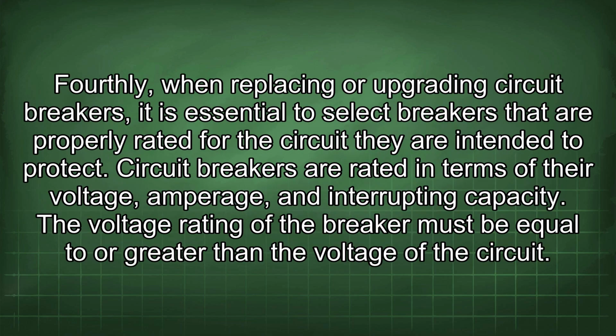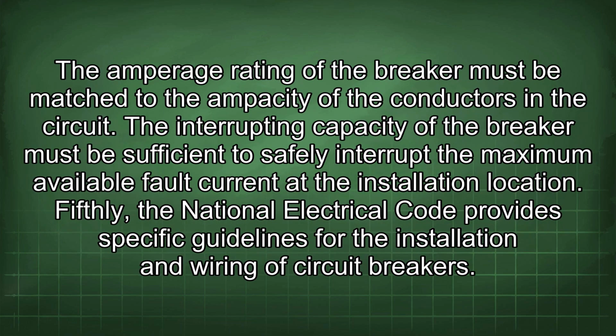Fourthly, when replacing or upgrading circuit breakers, it is essential to select breakers that are properly rated for the circuit they are intended to protect. Circuit breakers are rated in terms of their voltage, amperage, and interrupting capacity. The voltage rating of the breaker must be equal to or greater than the voltage of the circuit. The amperage rating of the breaker must be matched to the ampacity of the conductors in the circuit. The interrupting capacity of the breaker must be sufficient to safely interrupt the maximum available fault current at the installation location.